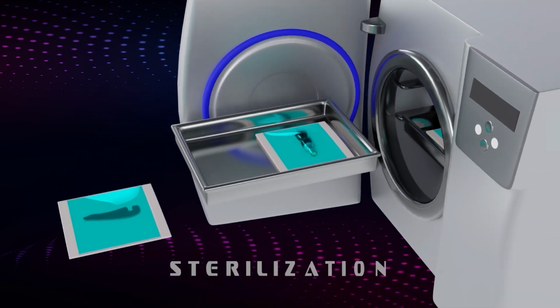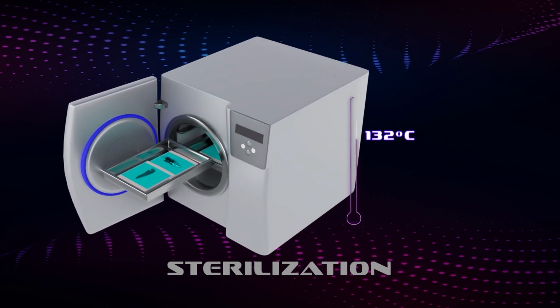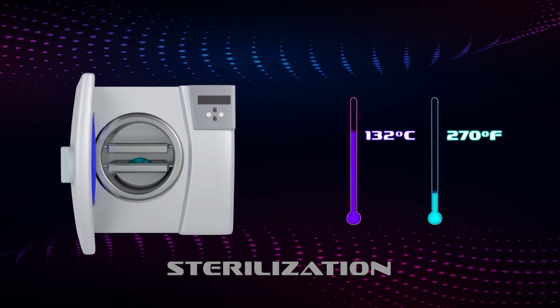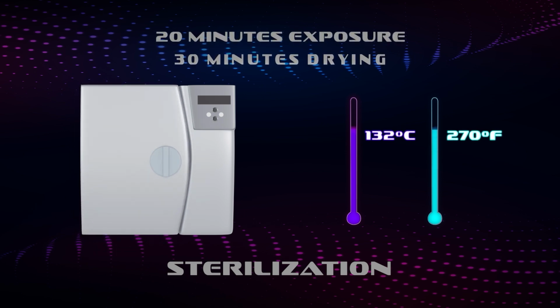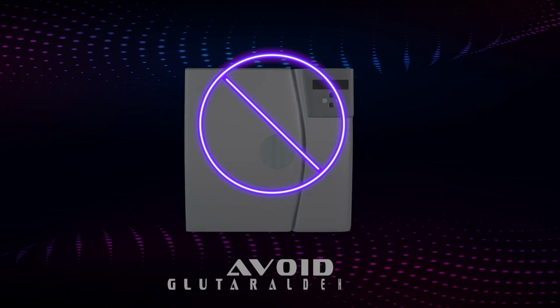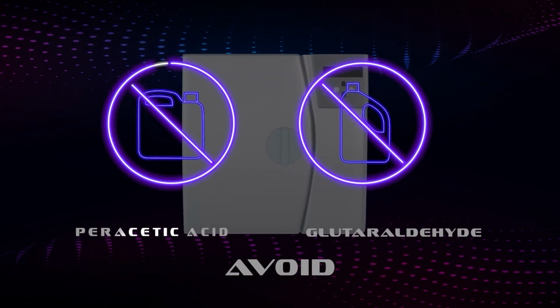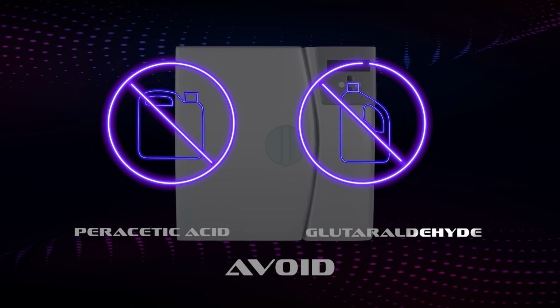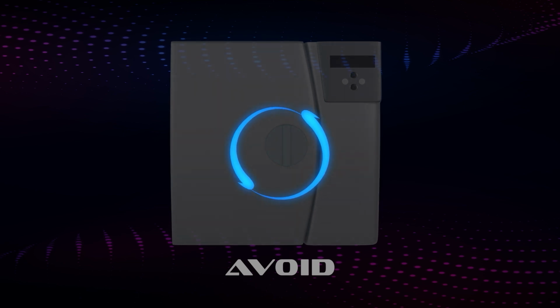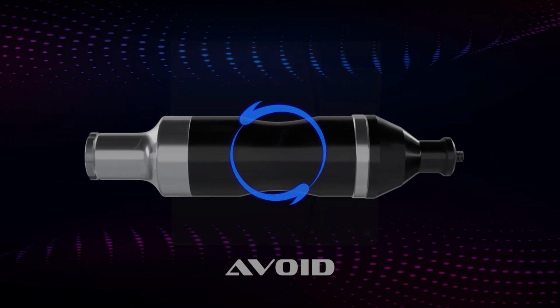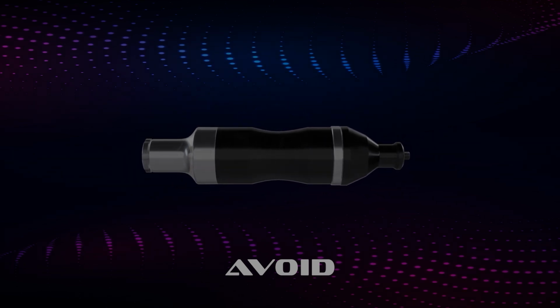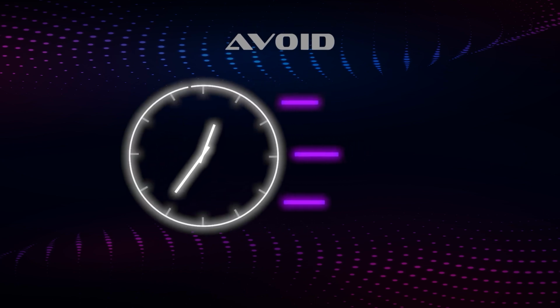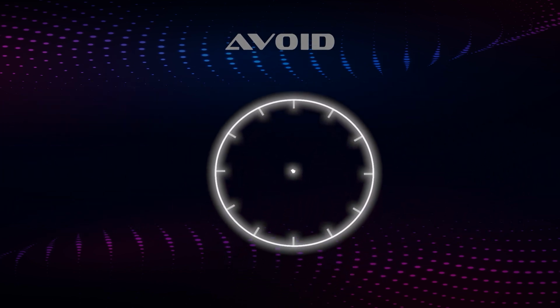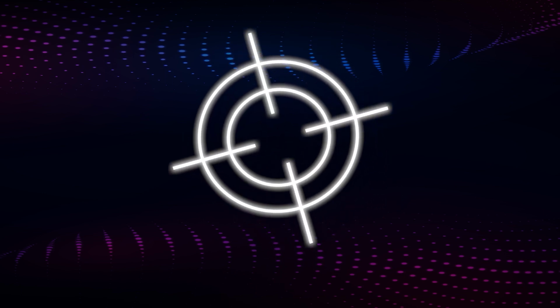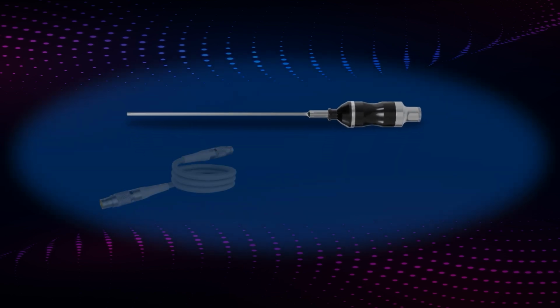The sterilization recommended by the manufacturer is an autoclave at a temperature of 132 degrees Celsius or 270 degrees Fahrenheit for 20 minutes of exposure and 30 minutes of drying with a maximum of 2 gravity wraps to be considered. Avoid using processes involving glutaraldehyde or liquid peracetic acid in any concentration in the sterilization of the handpiece. The use of longer autoclave cycles than the recommended ones may gradually reduce the performance and lifespan of the handpiece. Avoid performing rapid sterilizations for immediate use of the handpiece through an autoclave cycle. Before using the handpiece, perform a visual inspection to rule out possible damage to the different components.